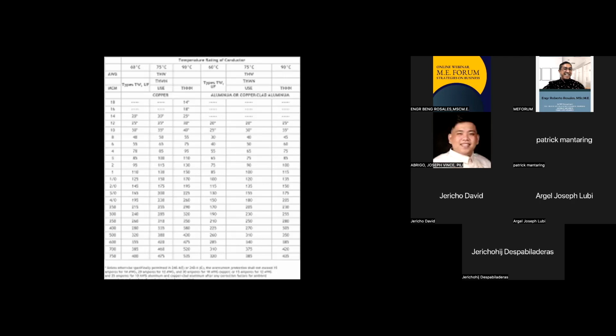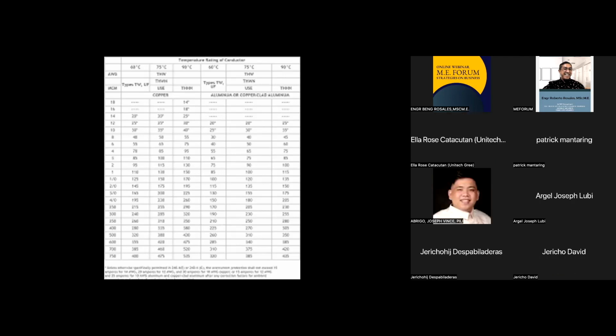Now, when you choose a wire, you need to understand that its ampacity should be higher than the breaker itself. Like I said a while ago, if you don't do that, your wire will burn before the breaker trips. Each wire has its own ampacity. Ampacity is the combination of two words, ampere and capacity. If you check the table, there is a list of ampacities you need to consider. For example, if you reach 35 amperes, your wiring should be size 10 in AWG, or 5.5 in the corresponding metric system. That is the basis for choosing a wire.